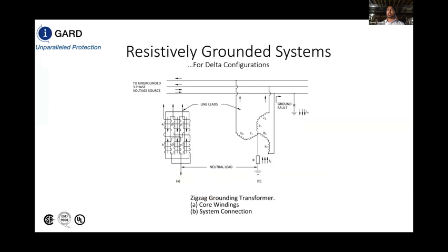Now, if your customer has an ungrounded system and they're complaining about transient overvoltages and difficulty in locating faults that are existing in their system, one way that we help our customers is we implement a zigzag transformer connected to the 3 phases. And this zigzag transformer establishes an artificial neutral, in which case we can connect a resistor from the artificial neutral to ground.